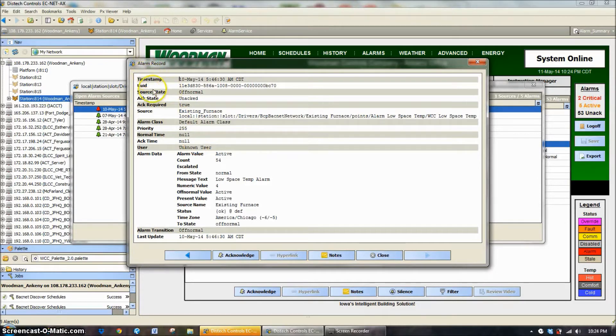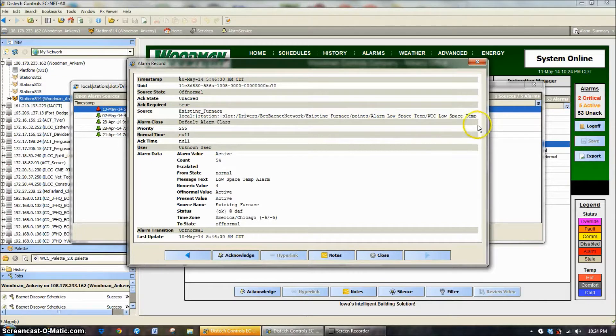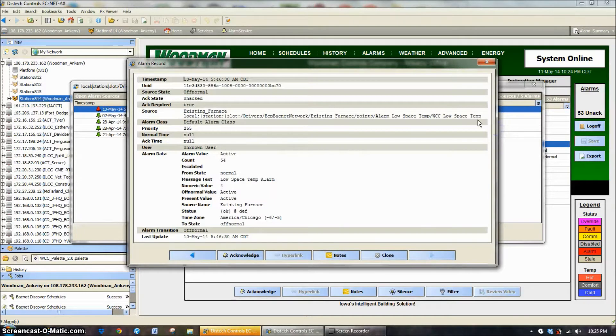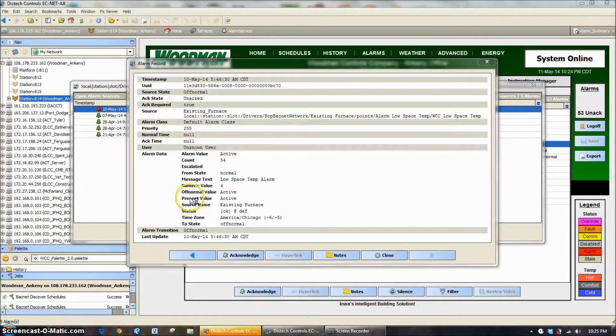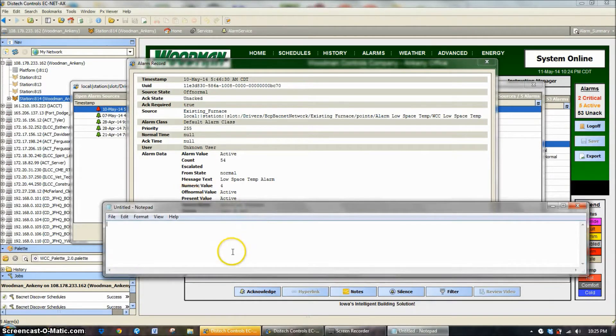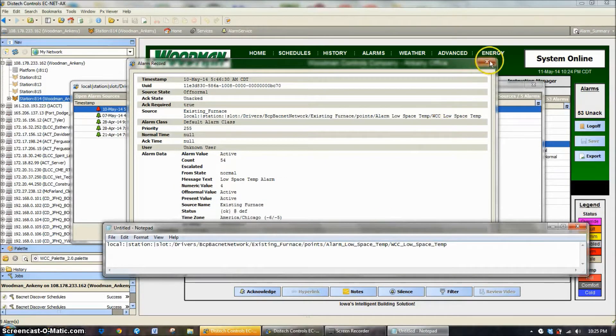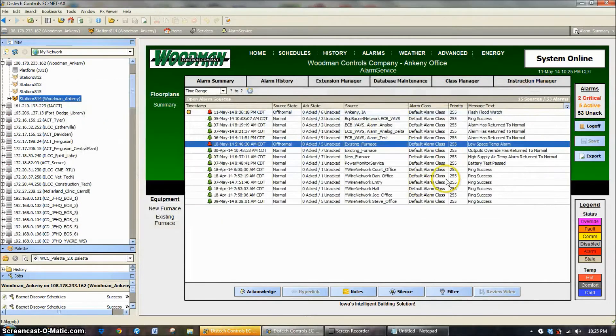On these alarm records, this is how you would track this alarm extension down. You want to look for the source. In this case, it's local station, slot, on down the list, and we're looking for the existing furnace and alarm low space temp point, and then there's an alarm extension on there. I'm going to take that point and copy it into a notepad file, that way I can remember where it is because once I click away from here it'll be hard to remember.